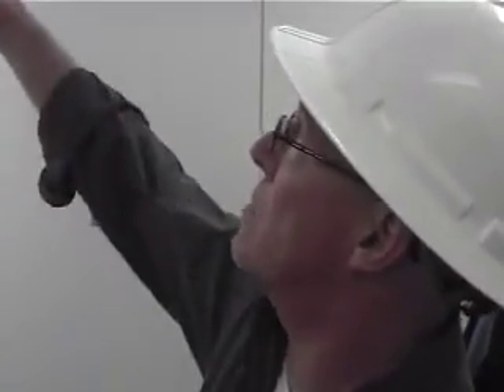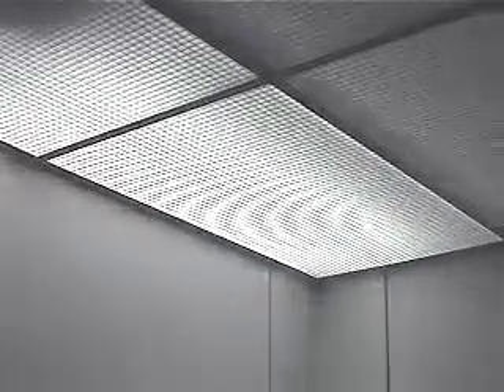You see we have a center ceiling mount coil. It's 2-way, so it draws in the bottom and blows out both ways. The ceiling is put in there for a couple of reasons. It helps with fluid air distribution. You don't have a direct airflow in one spot. Plus it softens the light a little bit. It just gives it more of a laboratory feel. Those panels can pop right out. They're not a big deal.